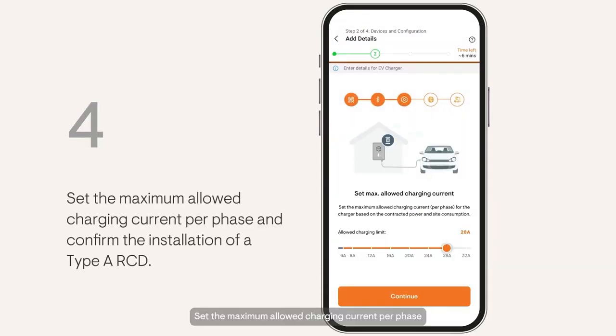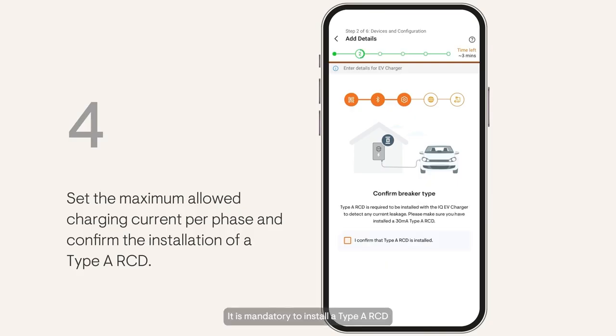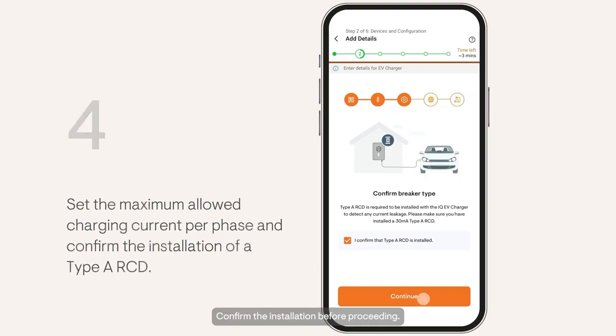Set the maximum allowed charging current per phase anywhere between 6 amps to 32 amps, based on the contracted power and site consumption. It is mandatory to install a Type A RCD to ensure protection against leakage currents. Confirm the installation before proceeding.